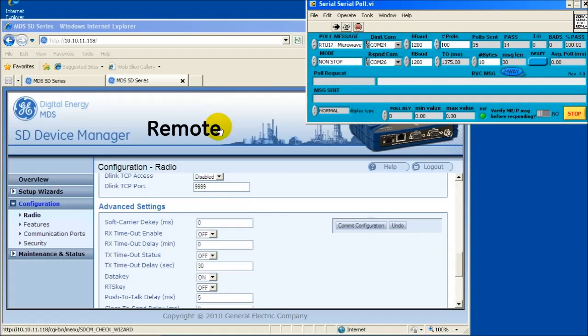The overall performance has improved. As the SD manual states, the baud rate should always be matched to the modem speed or higher, but in special circumstances where the PLC or RTU device is unable to be configured that way, adjusting the data key timeout feature will help optimize for better system performance.